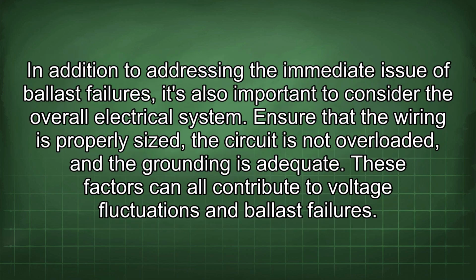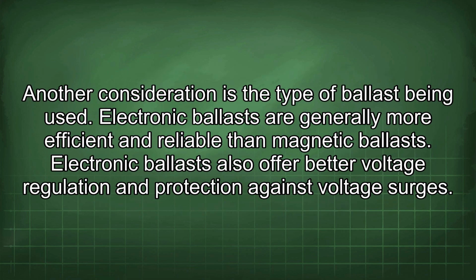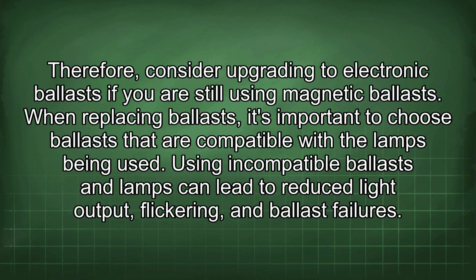In addition to addressing the immediate issue of ballast failures, it's also important to consider the overall electrical system. Ensure that the wiring is properly sized, the circuit is not overloaded, and the grounding is adequate. These factors can all contribute to voltage fluctuations and ballast failures. Another consideration is the type of ballast being used. Electronic ballasts are generally more efficient and reliable than magnetic ballasts. Electronic ballasts also offer better voltage regulation and protection against voltage surges. Therefore, consider upgrading to electronic ballasts if you are still using magnetic ballasts.